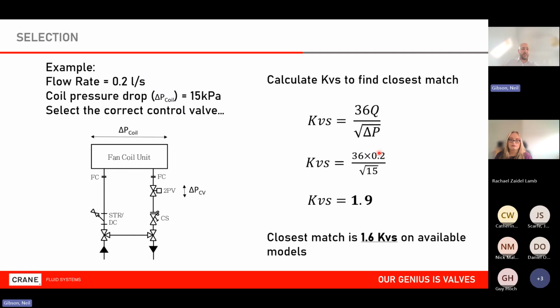How do we achieve that? Let's take an example. I've got a design flow rate, based on heat load, of 0.2 litres a second. Based on that design load and how I've selected my fan coil unit, the differential pressure across that is 15 kPa. My target for the control valve is 15. I use this calculation here to determine what my KVS, the valve coefficient, should be: 36 times flow divided by the square root of delta P. Plug in the numbers and I get a theoretical 1.9.